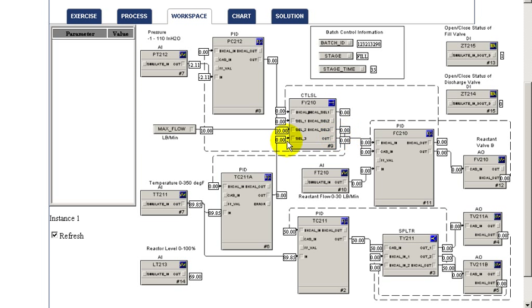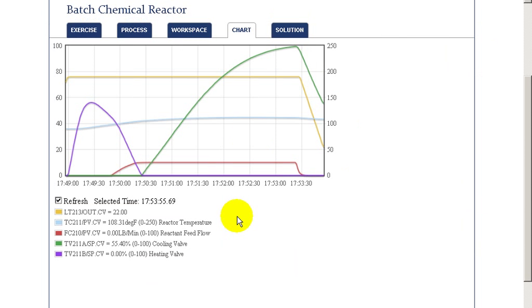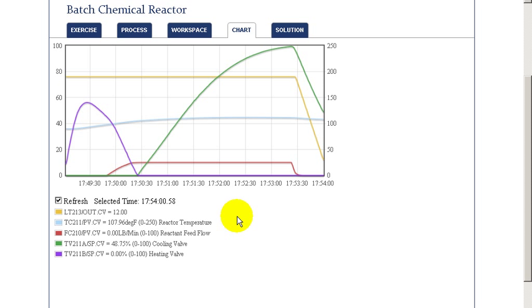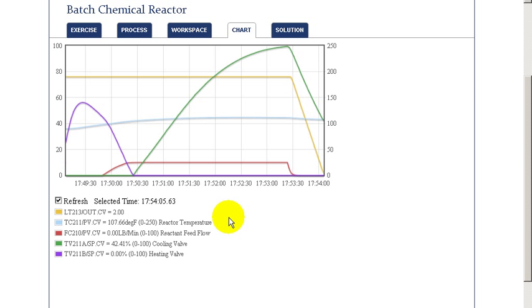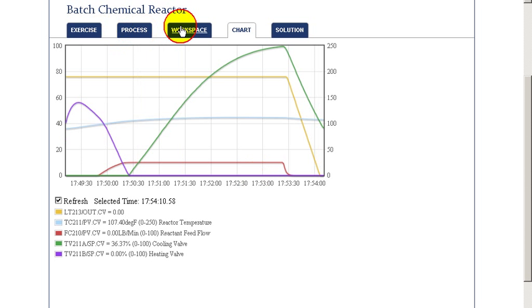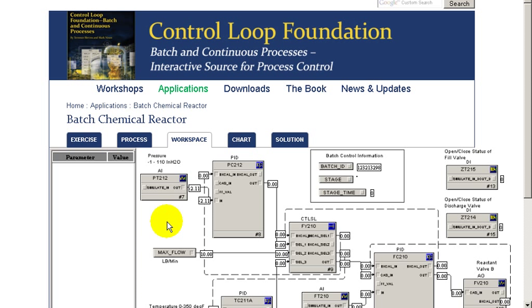As we can see in this case with a value of 12 for the feed rate, the cooling valve in the cycle had to go almost fully open. Let's look at what happens if we change it by more than that.